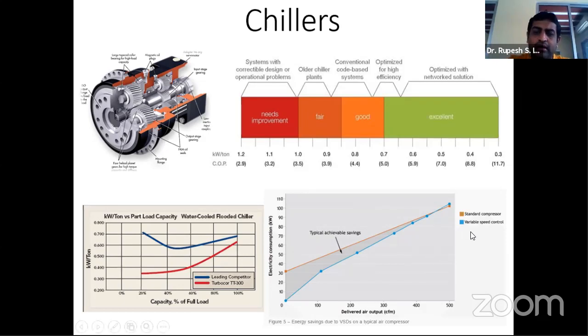Then the second could be a VSD itself, which could be put on a compressor. So the VSD would give us a savings of about 25 to 30% on that itself. So a magnetic chiller with a VFD could be a double energy efficient scheme on the chiller side.